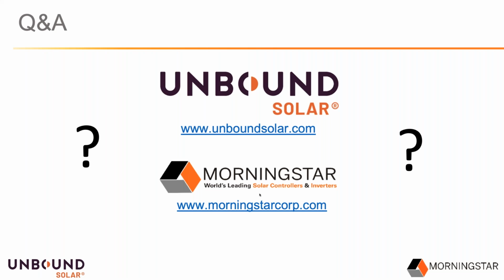Yeah, that's a good question, and I bet the most common issue that comes up in terms of inverters and washer dryers is that particularly newer appliances don't have enough power factor correction built in. Or I guess you could blame it on the appliance company, or you could blame it on the inverter company and say some of these don't have enough power factor correction built in, and that's what seems to be causing these issues, at least in our experience. There are some write-ups where folks will actually add a run capacitor into their appliance. It's usually a small separate box you'd wire it into, but basically the addition of a small inexpensive capacitor in the right part of the circuit fixes that issue with it not having enough power factor correction. And we have seen this come up with a few inverters. It seems like some brands are maybe worse than others.